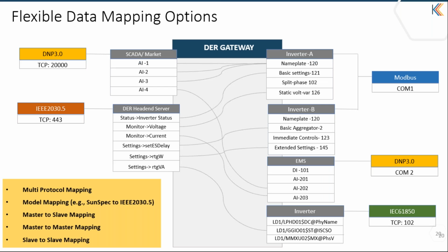Talking about the different protocols, the gateway needs to have a flexible data mapping option. In this example, there are different types of equipment communicating on different protocols, and the same data needs to be shared with external systems - one on 2030.5 to a DER headend, and the other a SCADA system on DNP3. So the gateway should have the flexibility to map this.